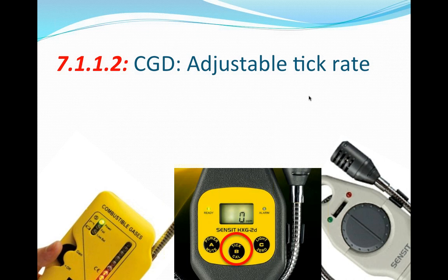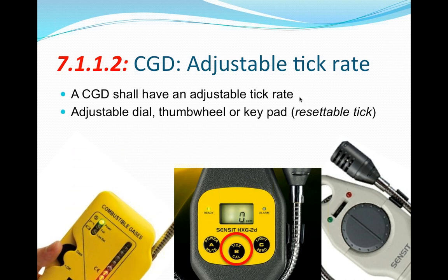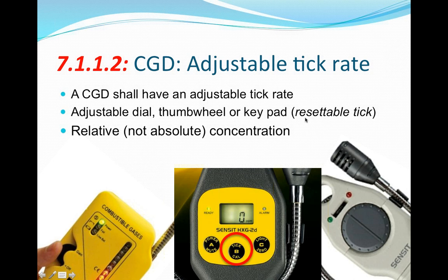Section 7.1.1.2 talks about a combustible gas detector that has an adjustable tick rate. They're looking for one that has an adjustable tick rate, and from that I divine that it's looking for something that has an adjustable dial, like the Leakator 10 here does on the left, or a thumb wheel or a keypad, like you see on the Sensit HXG2D, or a thumb wheel in the Sensit TKX, or on the Bacharach Leakator Junior, which has an adjustable range, a high-low range. So it's looking for a way to allow you to adjust the tick rate so you can home in on the source of the concentration.